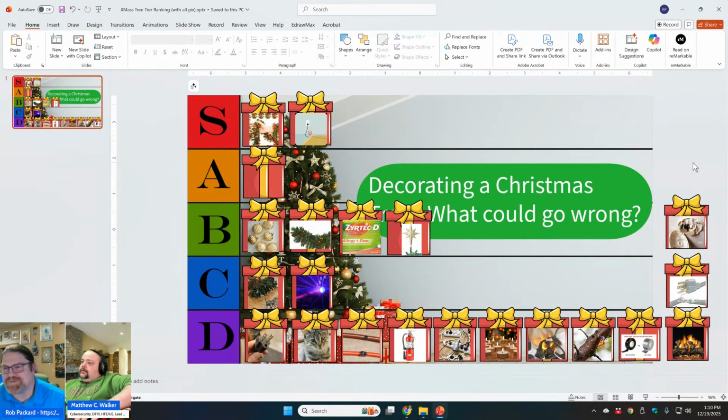So that's our list. Yeah, a general rule of thumb is that the FDA requires validation testing for everything associated with a critical task. Based on the ranking of our hazards here, if the use error applies to almost all of these, we're looking at a large series of critical tasks. I don't think this medical Christmas tree is going to be the type of device that gets to submit its regulatory submission without performing usability testing. Well, I mean, if it's a 510(k), all we have to do is show it's equivalently dangerous to everything else on the market. Whereas if we're doing a de novo, they're actually going to put the bar a little bit higher, and they're going to say this actually has to have benefits that outweigh the risks. And with that number of risks, you're probably out of luck this year.